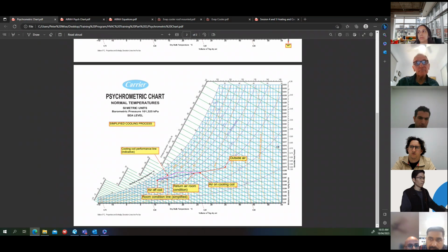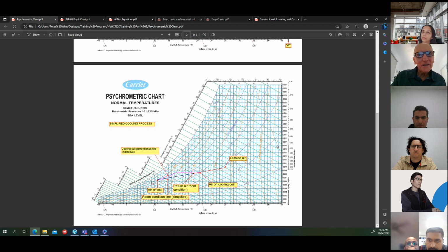You can calculate this, and I haven't prepared for that, so I'd have to go back into DA09 myself and have a look, because it gets a bit complex, but it's in DA09 and you can read that and determine how that's worked out manually. All the equations are in Camel to do those calculations. It calculates the apparatus dew point, determines where the apparatus dew point is on the saturation curve, and then works out what the air off condition would be. Not a very good explanation, but it is quite complex, and there's a lot in it.